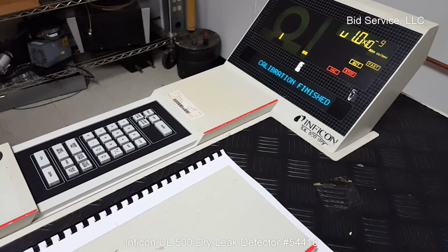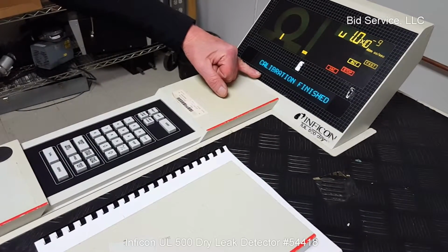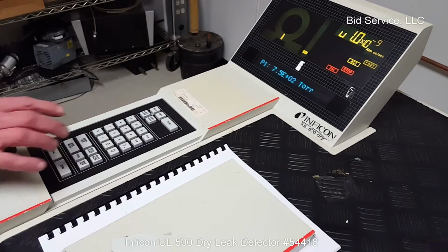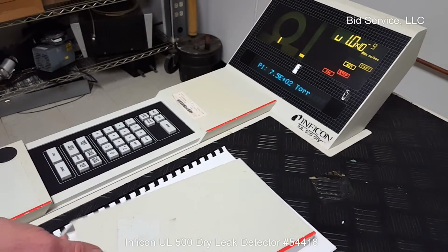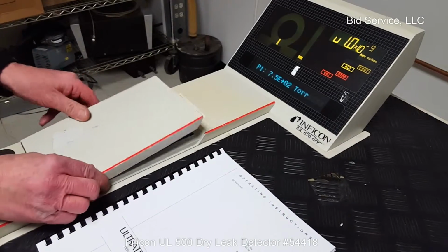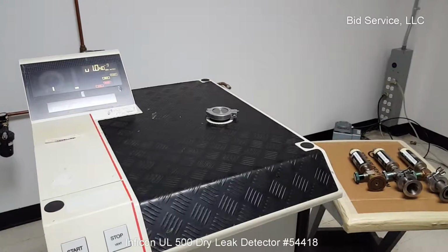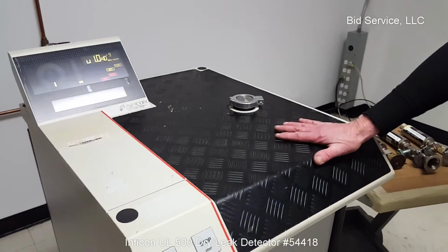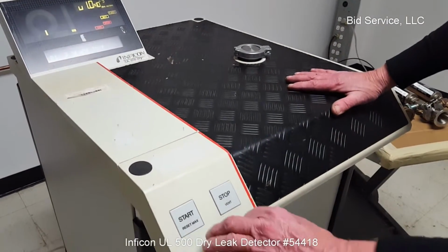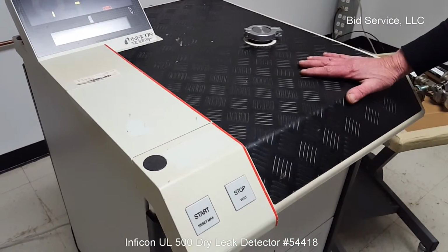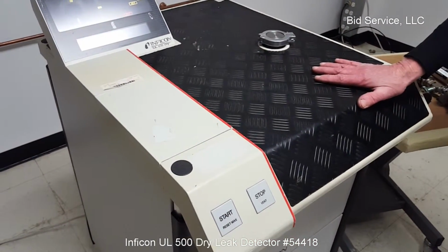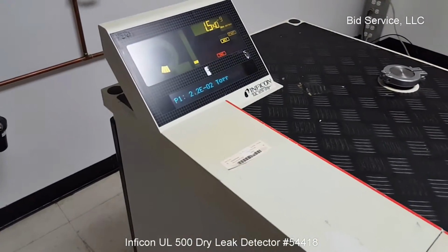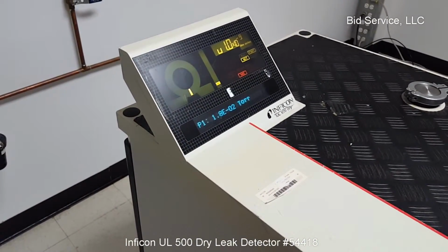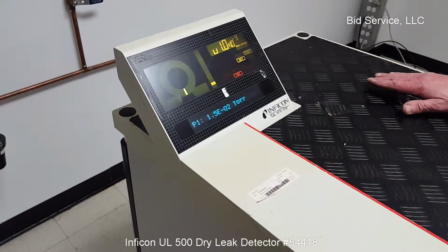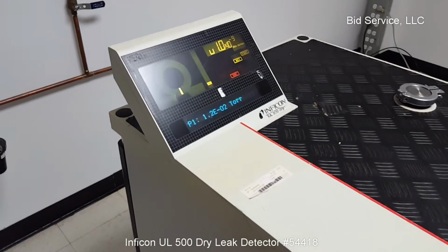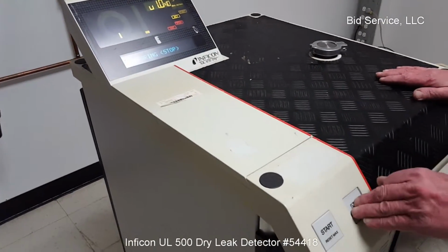Once calibration is finished, it'll show you on this display, and then you can just hit clear, and the system is ready to use and ready to test your workpiece. Once the system is set up to actually operate a test, it is as simple as pushing the start button. In this case, the system is pumping against itself. It is blanked off. And to stop your test, just push stop, which also vents the test chamber.